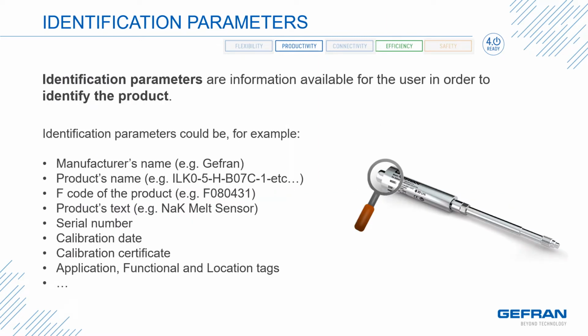Identification parameters are just that. It's very specific information available to the user in order to identify the product. For example, manufacturer's name, the product name, that's the complete code of the product, a part number, some text that can be stored at the time the sensor is commissioned, serial number, calibration date, calibration certificate, application, functional and location tags, and the list can go on.